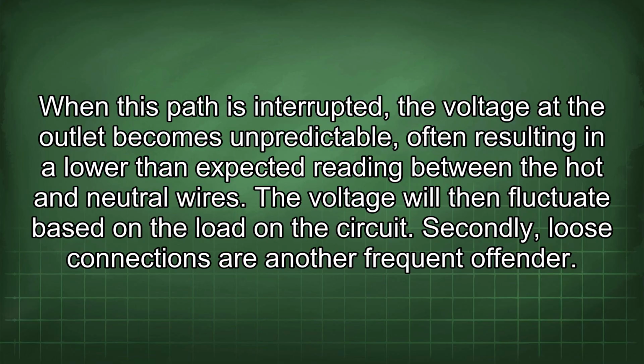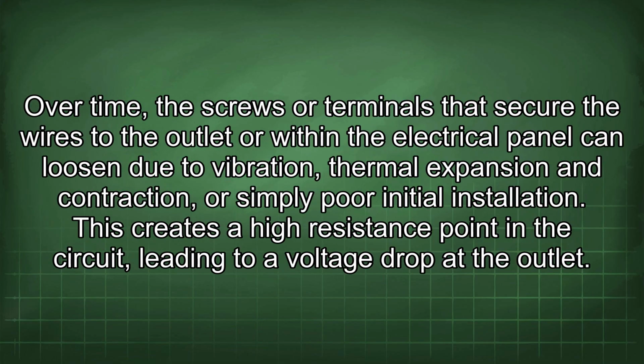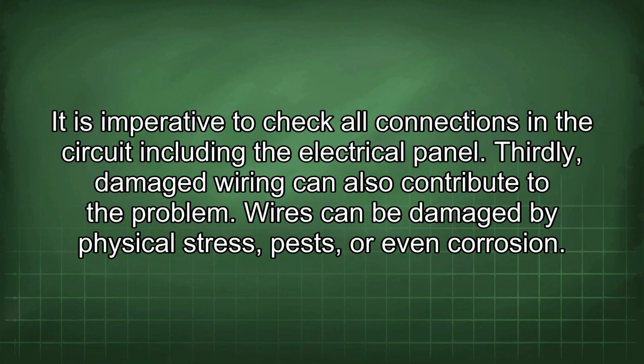Secondly, loose connections are another frequent offender. Over time, the screws or terminals that secure the wires to the outlet or within the electrical panel can loosen due to vibration, thermal expansion and contraction, or simply poor initial installation. This creates a high resistance point in the circuit, leading to a voltage drop at the outlet. It is imperative to check all connections in the circuit, including the electrical panel.